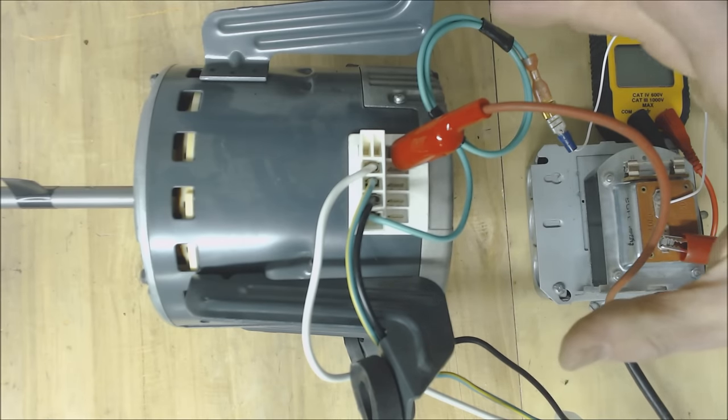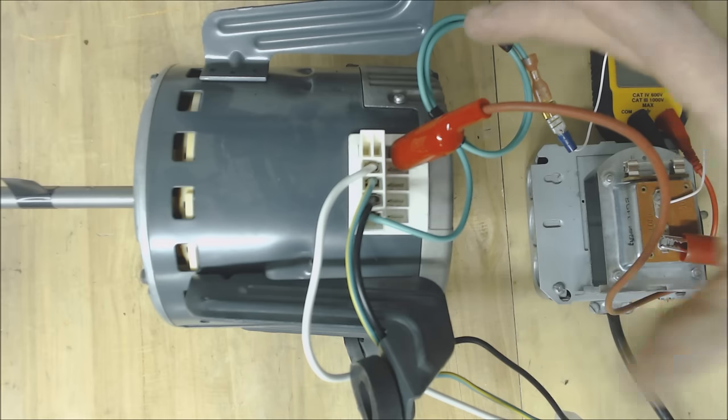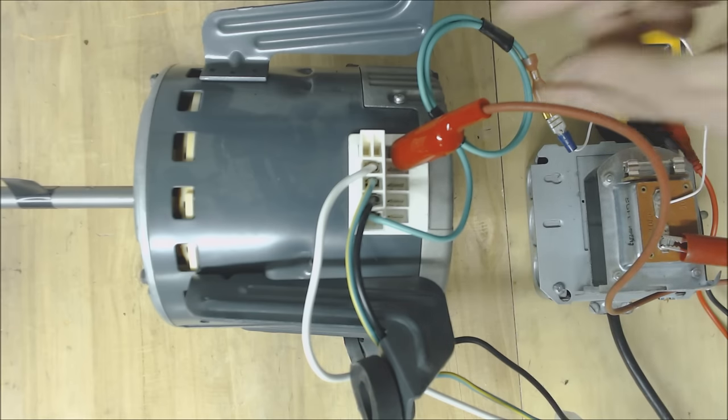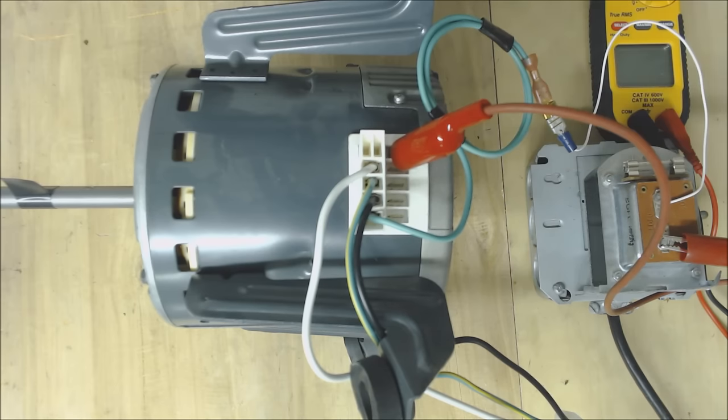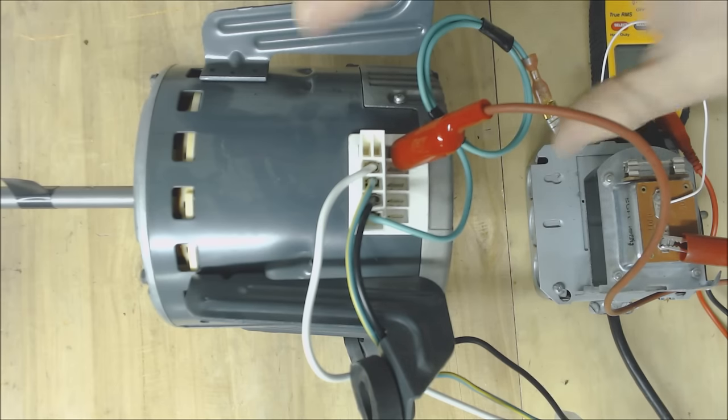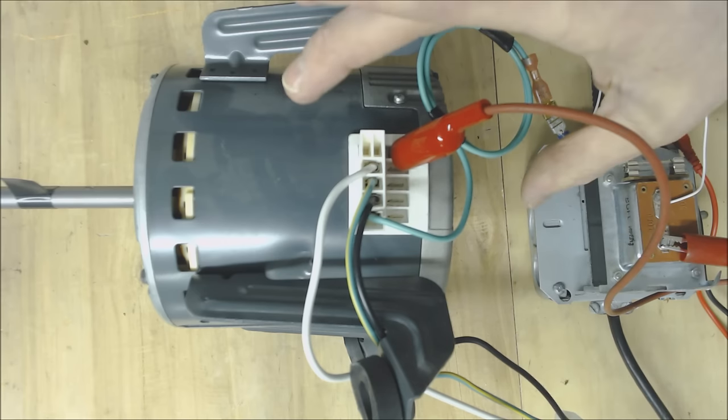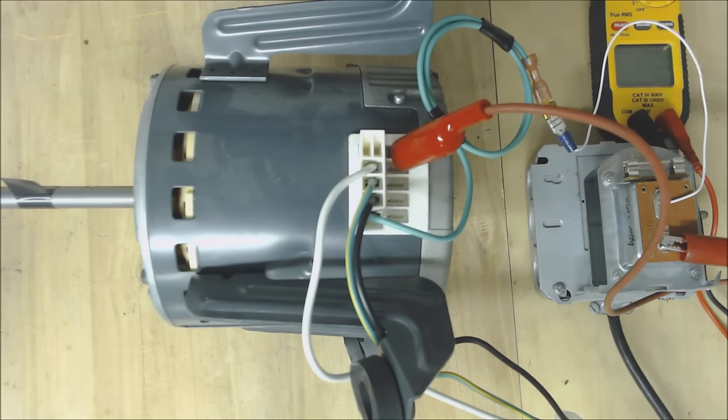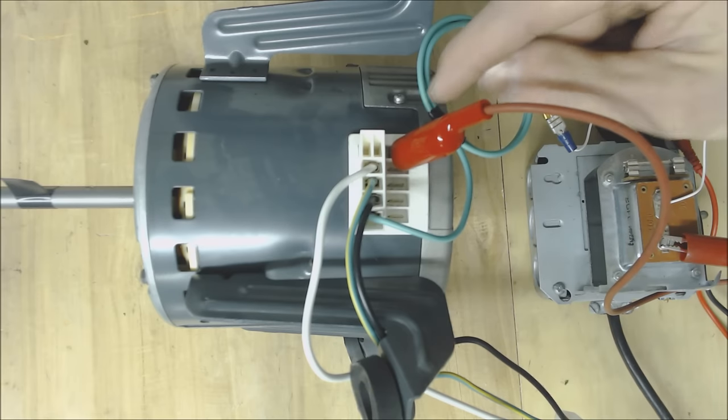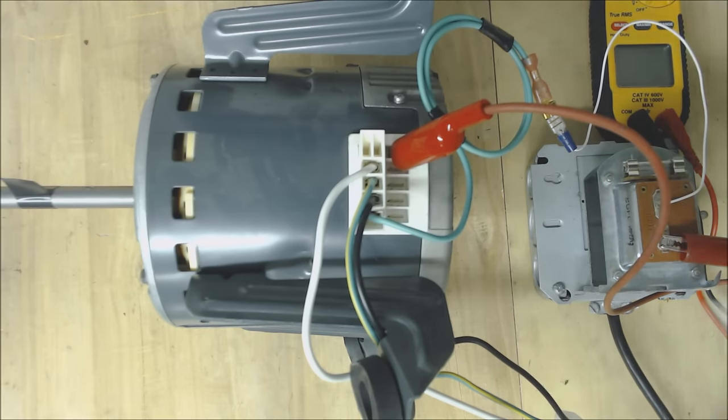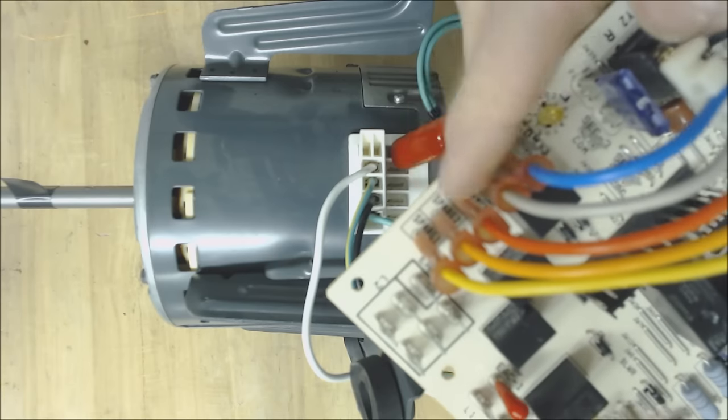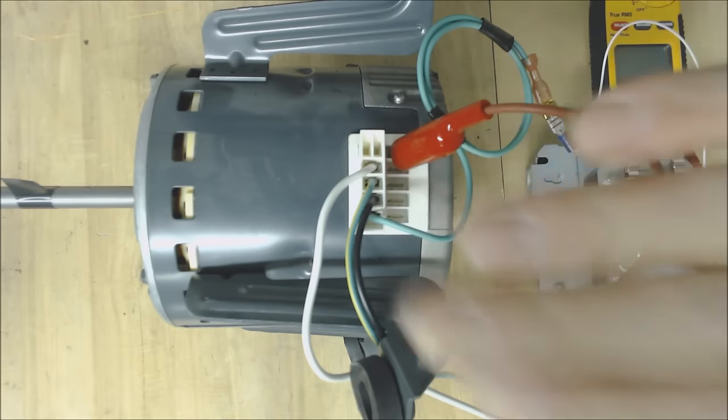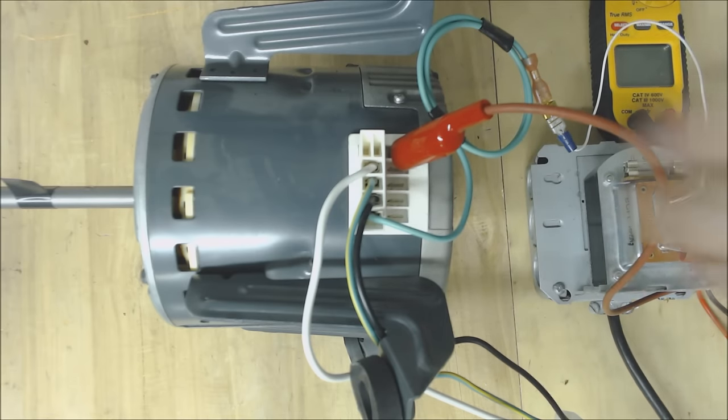In reference to troubleshooting these blower motors the best thing I can tell you to do is to have all of your electrical connections already tightened in. So in this case it's alligator jumpers. It's going to be a little different when you're in the field and this blower motor is in a furnace cabinet that's very tight. So what I would suggest you do is just have your alligator clip set up ready to go or your connection there and you're just reading your 24 volt signals at the control board. You want to make sure that you don't have your hands near the 120 volts or the 240 volts.